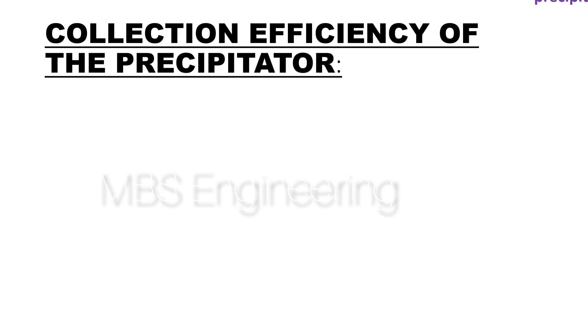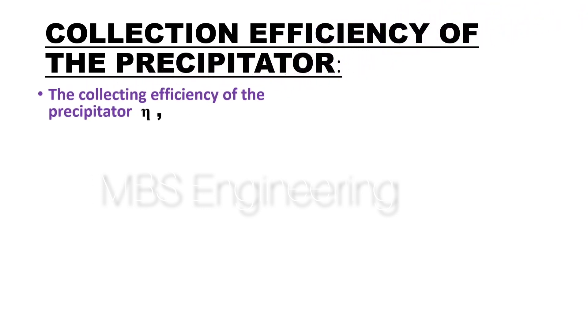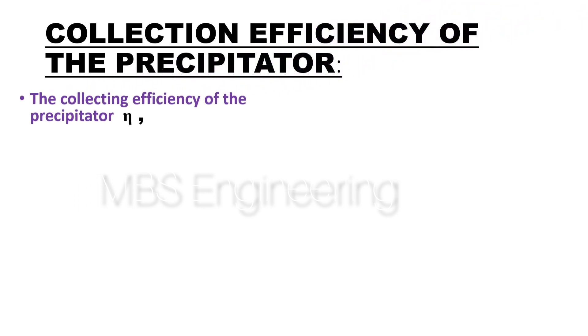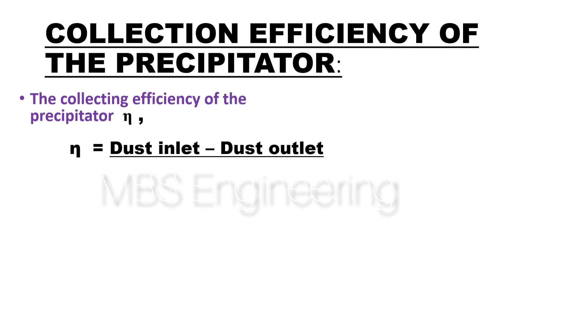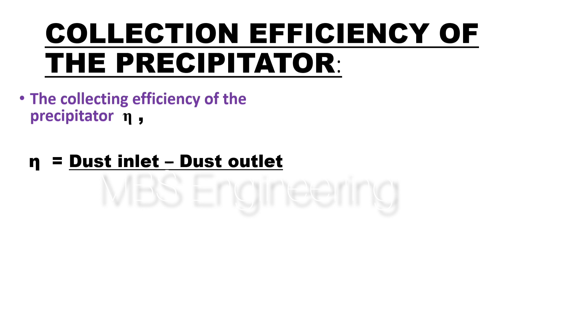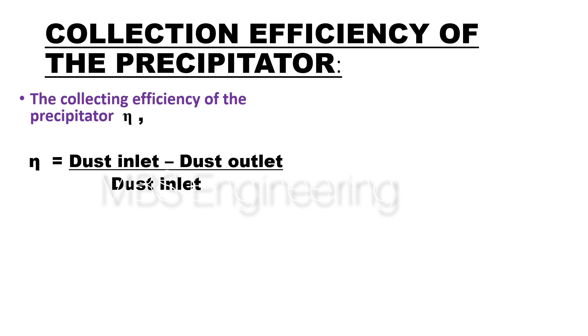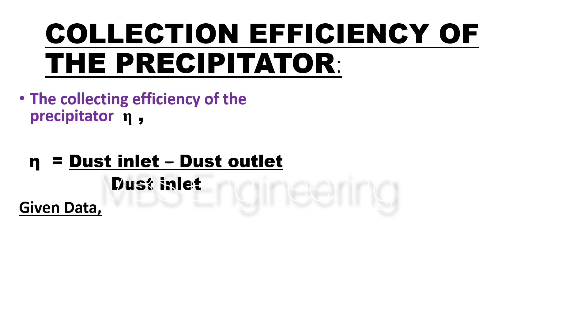Next, we are going to understand how to calculate the collection efficiency of the electrostatic precipitator, based on inlet and outlet dust concentration. The collection efficiency η is equal to inlet dust concentration minus outlet dust concentration, divided by inlet dust concentration.